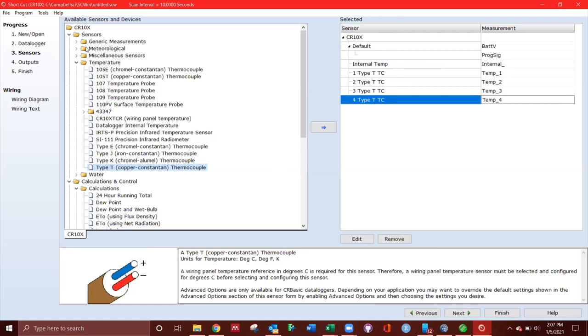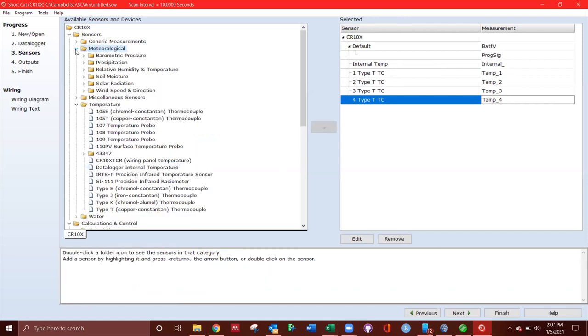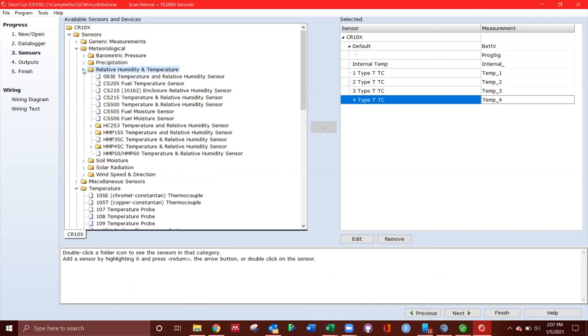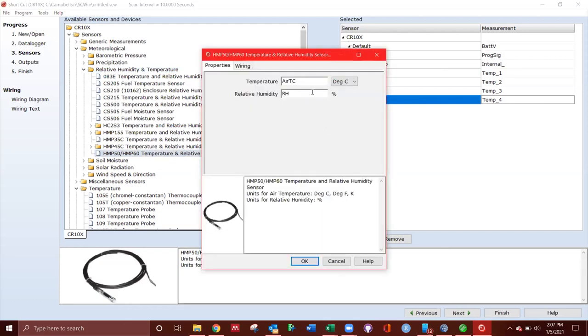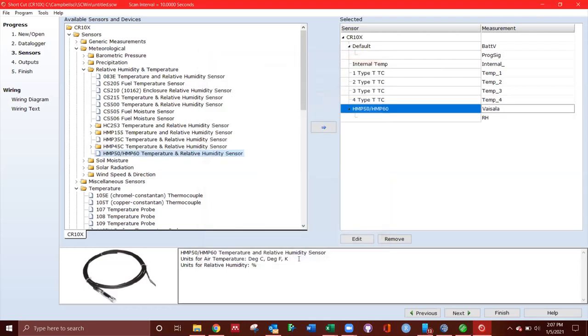So here we have all of these things. Now, what else I need to add, I want to go down to meteorological, relative humidity and temperature. And I have, I'm using a Vaisala sensor, which is an HMP 50 or HPM 60, or HMP 60 temperature and relative humidity sensor. So I'm going to go ahead and add this. Temperature is going to be, I'm going to call it Vaisala. And it's degrees C. And relative humidity is going to be called RH and percent.